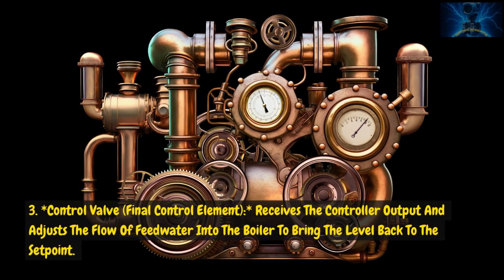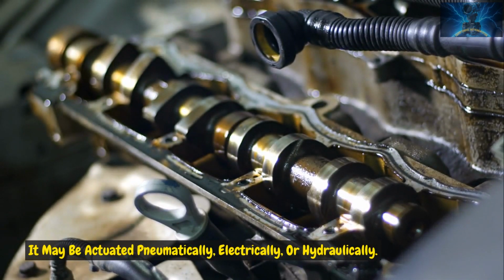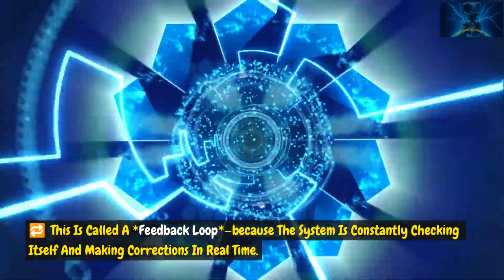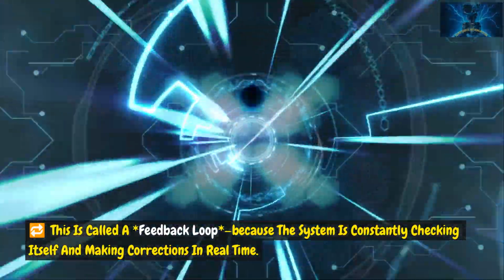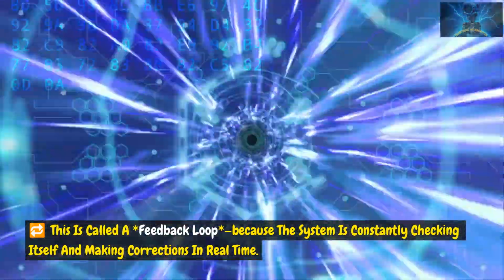3. Control valve, the final control element. Receives the controller output and adjusts the flow of feed water into the boiler to bring the level back to the set point. It may be actuated pneumatically, electrically, or hydraulically. This is called a feedback loop, because the system is constantly checking itself and making corrections in real time.